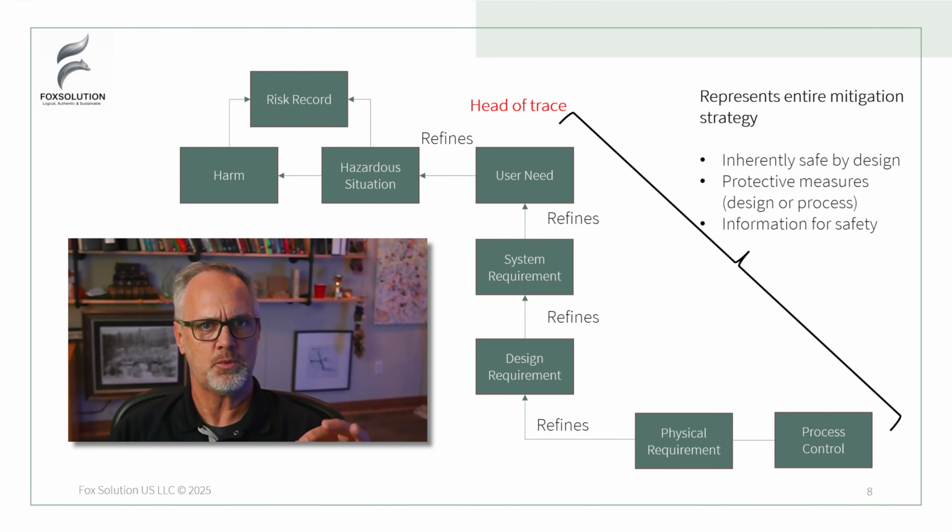So now each one of the hazardous situations has what's called a P1 factor. This is based on the 14971 risk management protocol, the appendix in that document. The P1 factor is how often that hazardous situation occurs. And that's carried inside the hazardous situation. This is the only thing really that we can adjust to mitigate the risk in our system. So we have a pre-mitigation P1 and a post-mitigation P1.